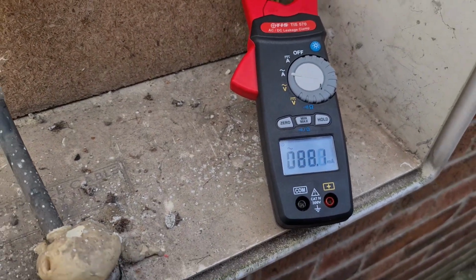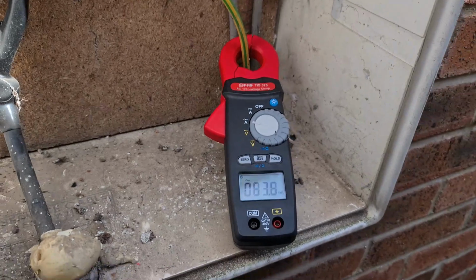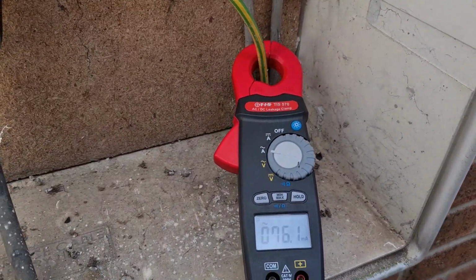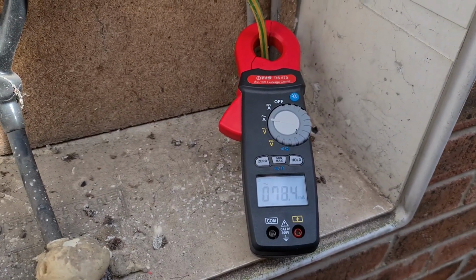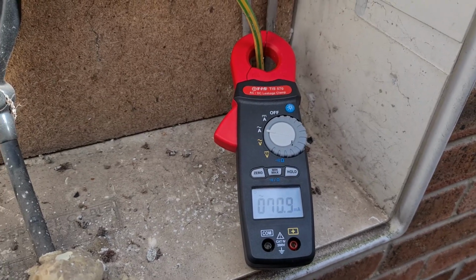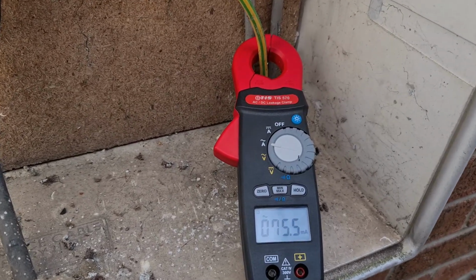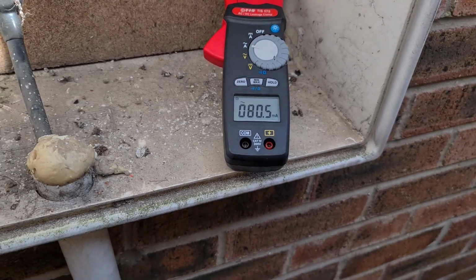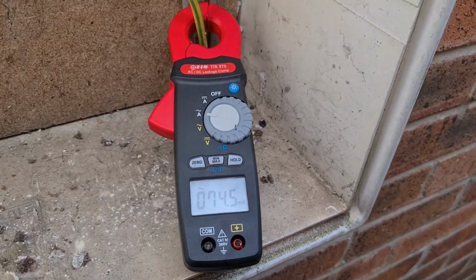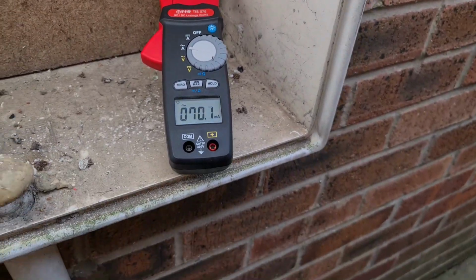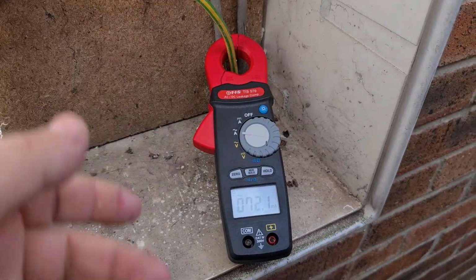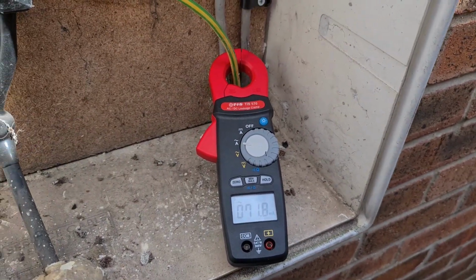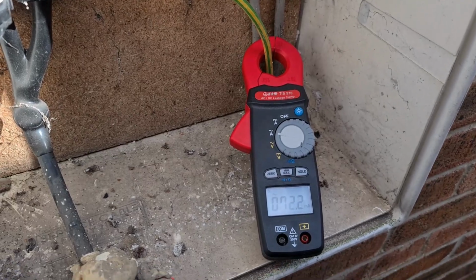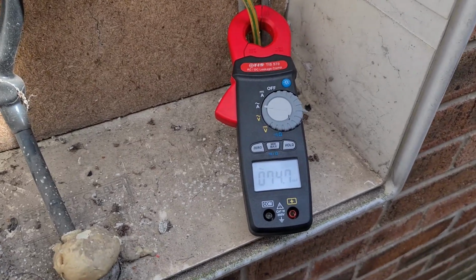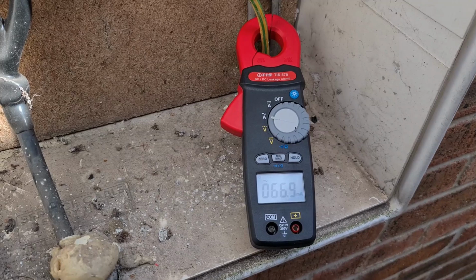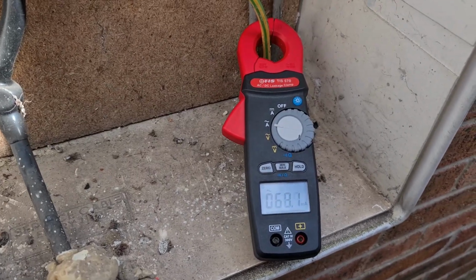Obviously when you're inside the potential zone and everything is connected, it's not such an issue, but when you're disconnecting conductors to carry out test measurements, you need to be aware there could be different potentials in close proximity to yourself where you might come into danger, so be aware of it. For example, if you are disconnecting the main earthing conductor and you've still got all of your protective bonds and you put yourself between those 2 points, you can make yourself part of that circuit. So just be aware of it and keep yourself safe.